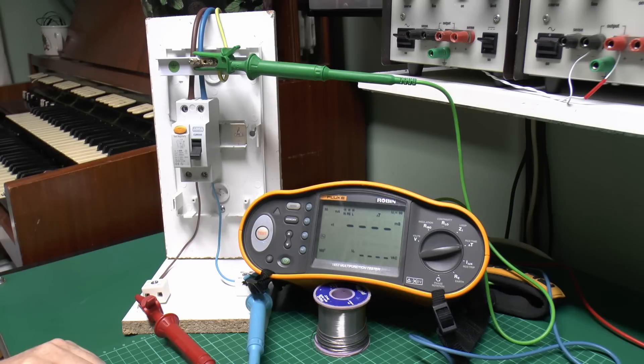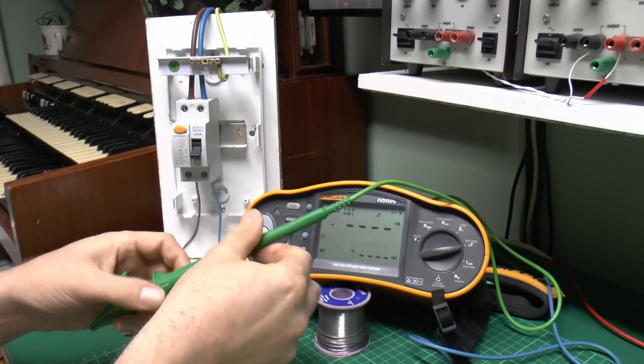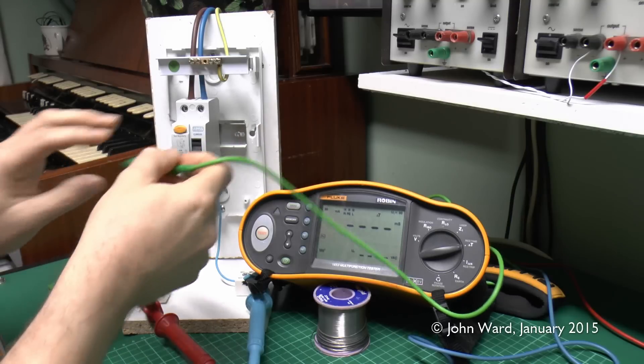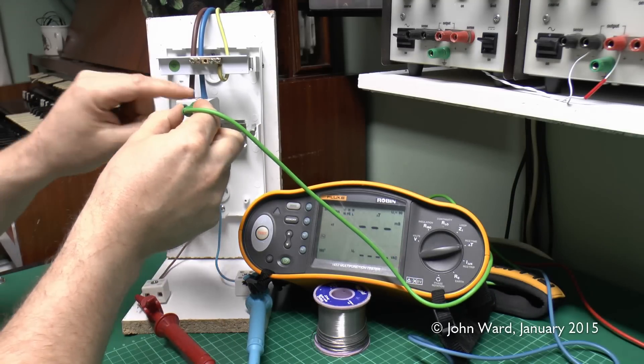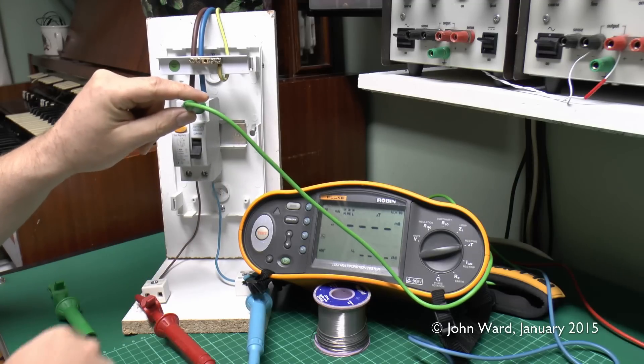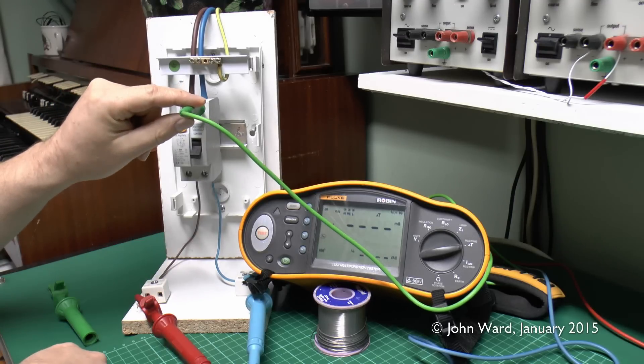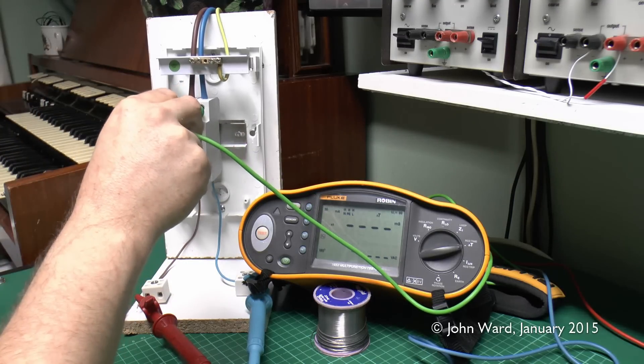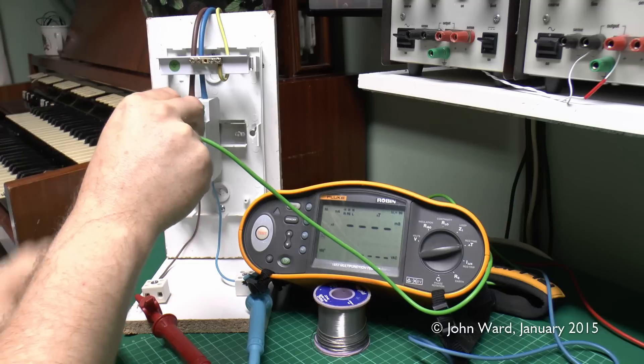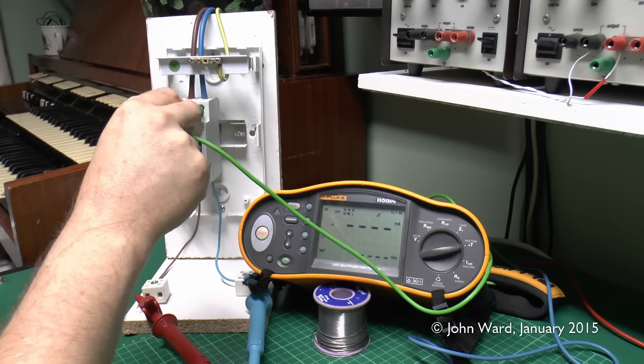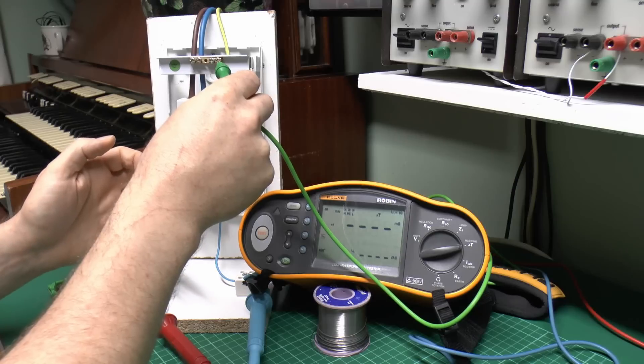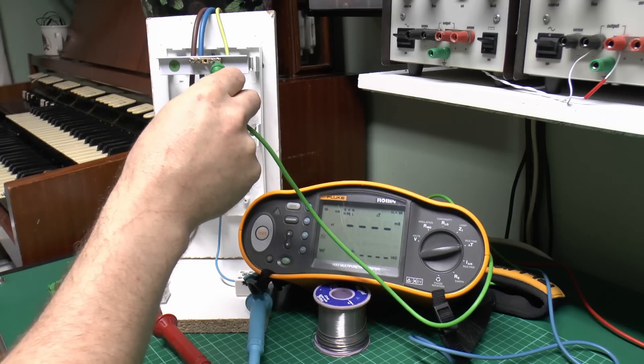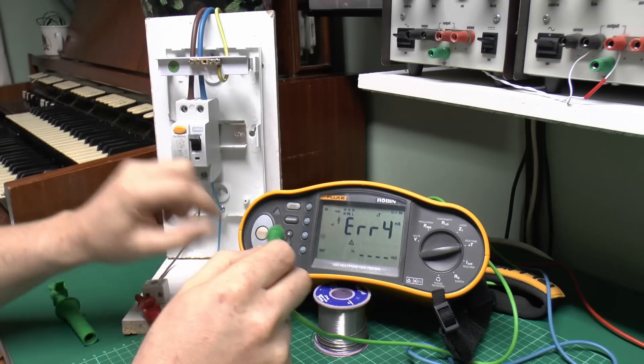But there's a handy thing to do which can get around this problem, and instead of connecting the earth to the earth here, what you actually do is connect it to the incoming side on the neutral here, and this will still trip this particular RCD, no problem, because it's still seeing an imbalance between here and here, obviously on the incoming and outgoing sides. But it won't trip any RCDs further up the chain because according to those they've just got the same current coming in both on the line and the neutral so they don't actually see the imbalance. Whereas if you were testing here on the earth as normal, the imbalance will be seen by both this device and other devices further up the supply chain.